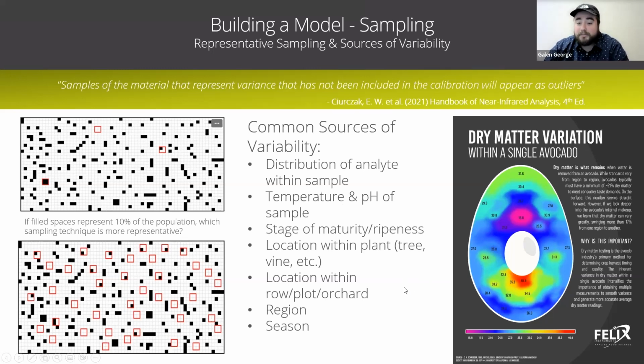Another source of variability is going to be the temperature and the pH of the sample. Both of those have significant impacts on spectra, especially NIR spectra. And I'll show you an example of that here in a second. So when you're doing your sampling, you want to make sure that you're doing your scanning with your instrument as well as your analytical testing, where your sample's at the same temperature, the same pH as it would be when you're doing it in practice. So you want to scan if you're out in the field, for example, and it's a really hot day and you're taking your sample scans. Then what you're going to want to do is make sure that when you go to do your analytical testing, the sample is at that same temperature as it was when you did your scanning.